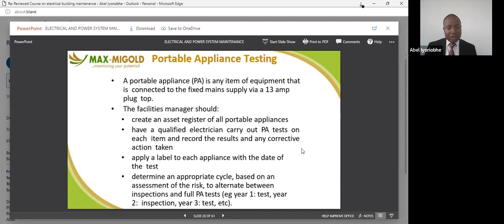Why do we create an asset register of all portable appliances? Have a qualified electrician carry out PA testing on each item and record the result and any corrective action taken. It can be a referral. Something happened, we may not be there. You are creating a process, because you may not be there tomorrow. Whoever steps into your office will go through your records and see such a thing has happened before. If a similar thing happens, it gives them room to adequately trace out the fault and correct it, because they already have the record and knowledge of what you have done. It's good to keep all your records. Don't just do it for the sake of meeting a target; do it for the sake of reference.